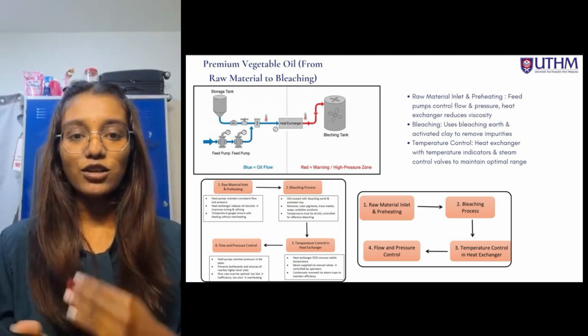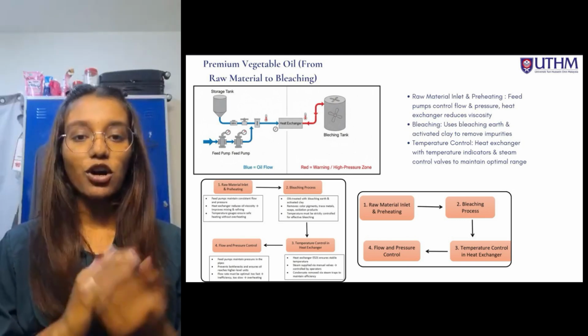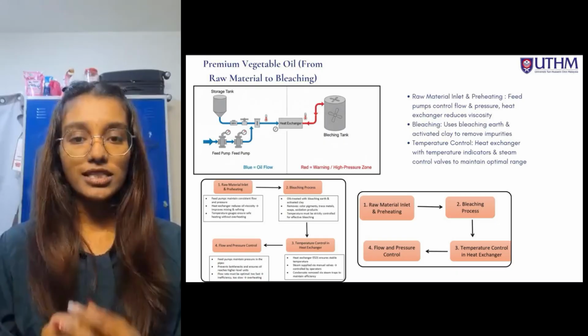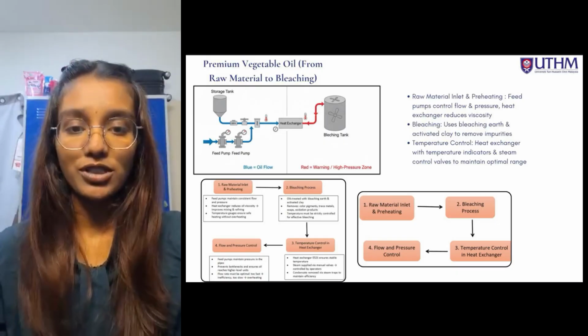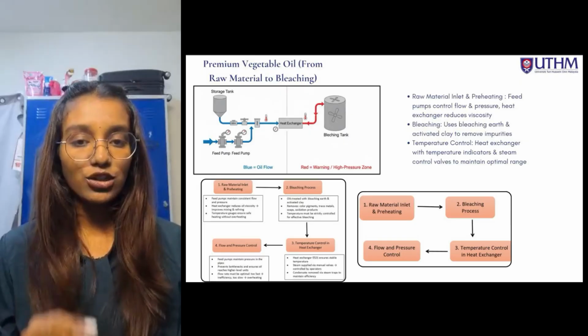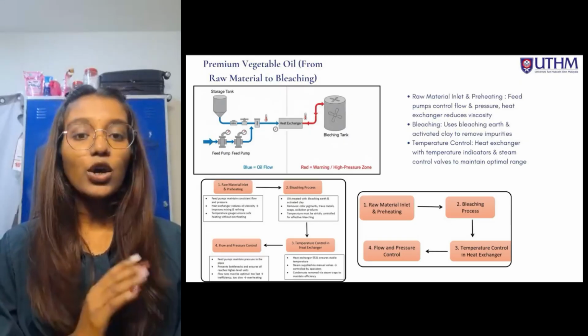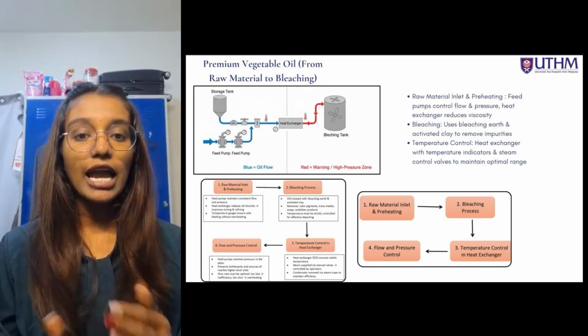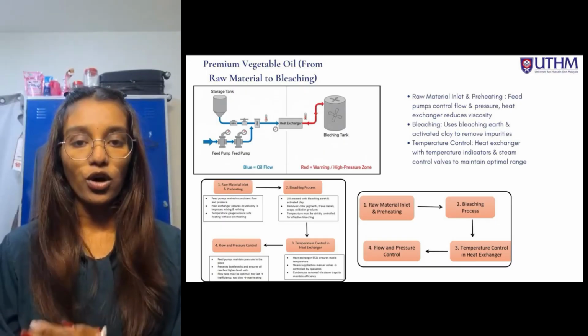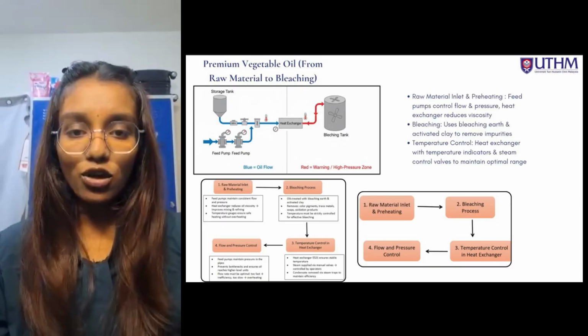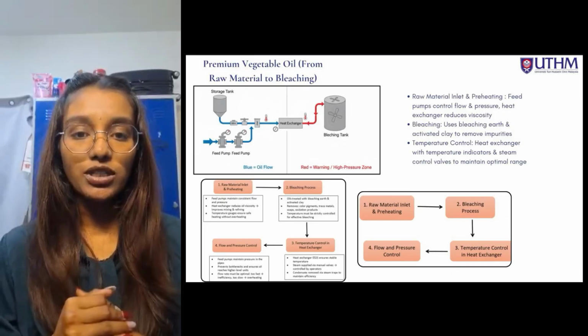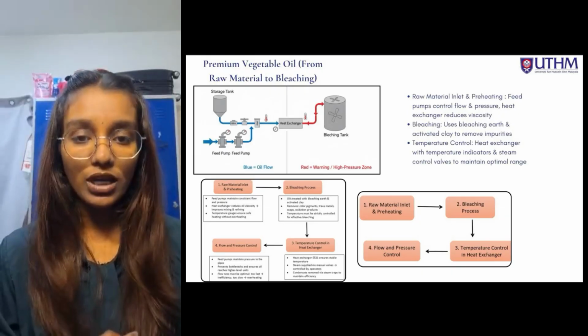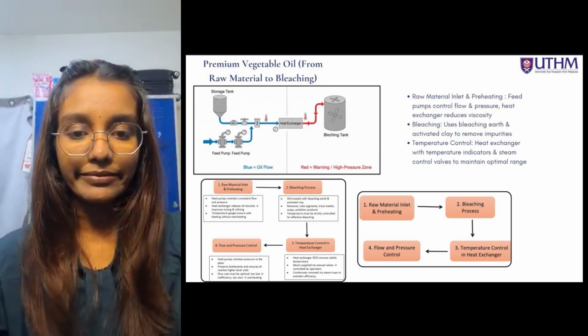Feed pumps here control both the flow and pressure of the oil, ensuring a consistent supply throughout the process. The heat exchanger reduces the oil's viscosity, which improves mixing and makes refining more efficient. Temperature gauges are also installed to ensure the oil is heated safely without risk of overheating.